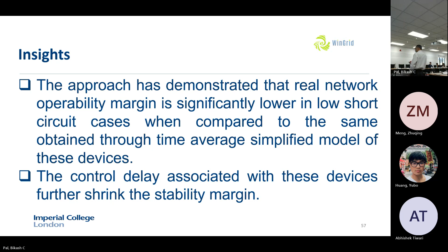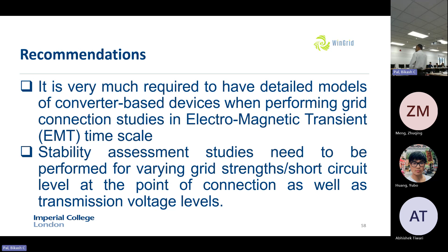So it is very much required to have the detailed model of converter-based devices when performing grid connection studies in the electromagnetic transient time scale. Stability assessment studies need to be performed for varying grid strength, short circuit level at the point of connection, as well as transmission voltage level. So TNO and TSO should insist on various other parametric sensitivity studies regarding key control schemes, interface PLL technology, etc. They must reveal what the PLL technology and topologies are, and the specification should be amended with these requirements so that any connection study adheres to these detailed specifications. So this is the work done by Nicholas, and some of the work is here.